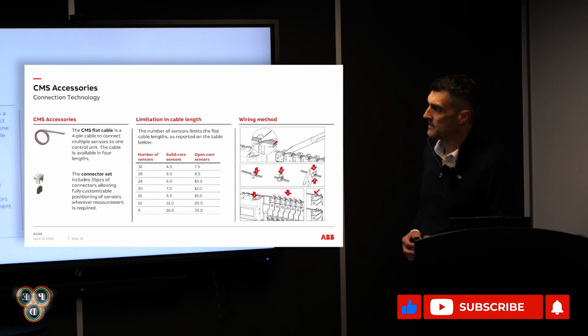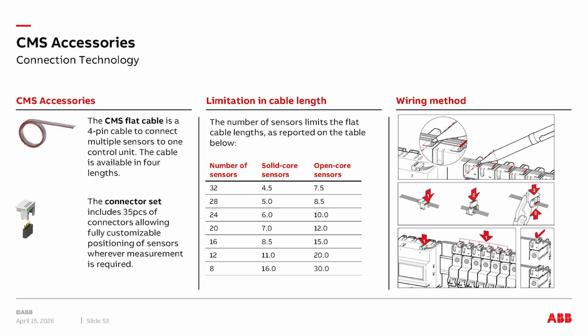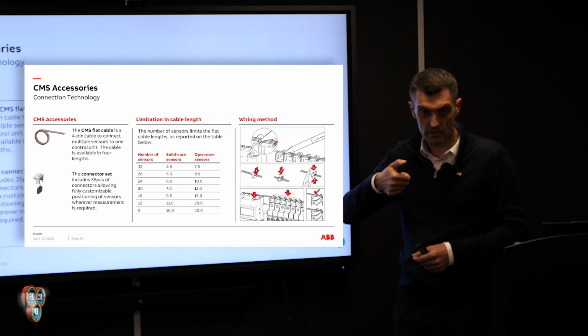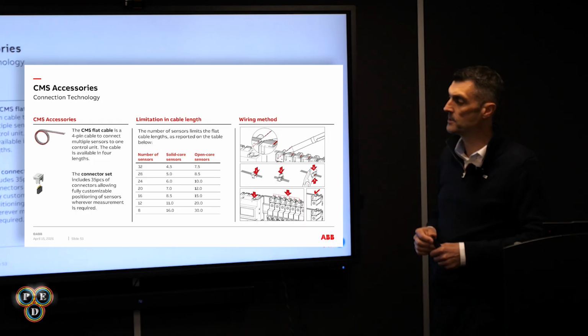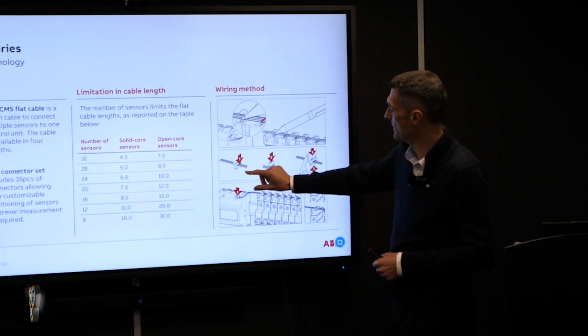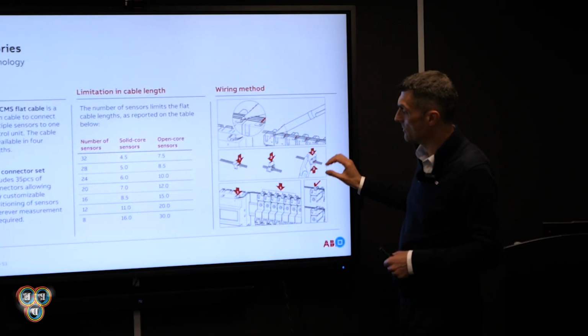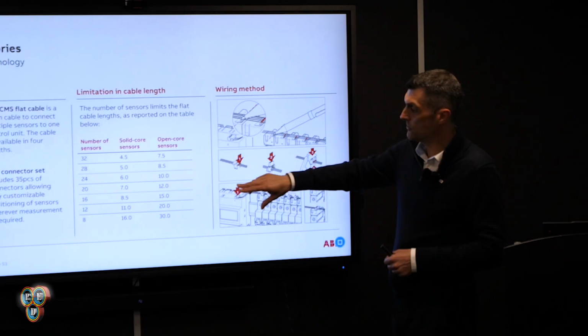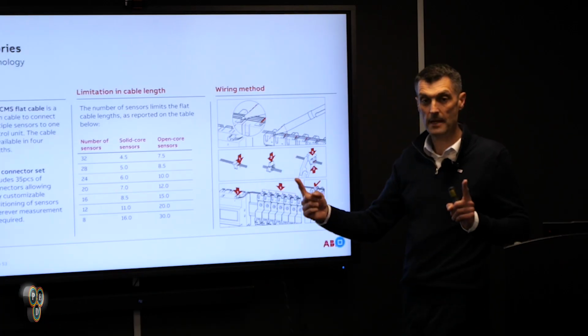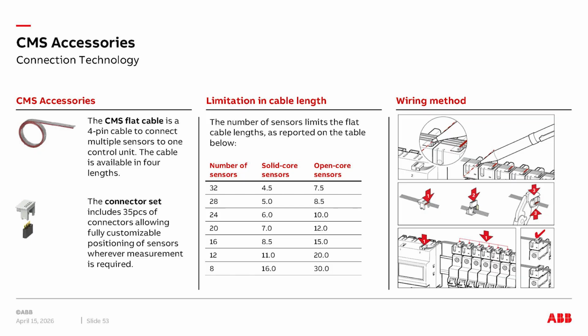The ribbon cable is nice and easy to install - you've got your flat cable and your connector sets. They come in a bag of 35, and you just need a pair of long nose pliers to clip these on - no special tooling, no special procedures. You can fix the connectors anywhere along the cable, although the more connectors you use, the more you shorten the maximum permissible length of that cable. But when you get to the specification stage, we can forward you this table so the guys know exactly what they're doing. The ribbon cable comes in, I think, 5 meter up to 30 meter lengths.